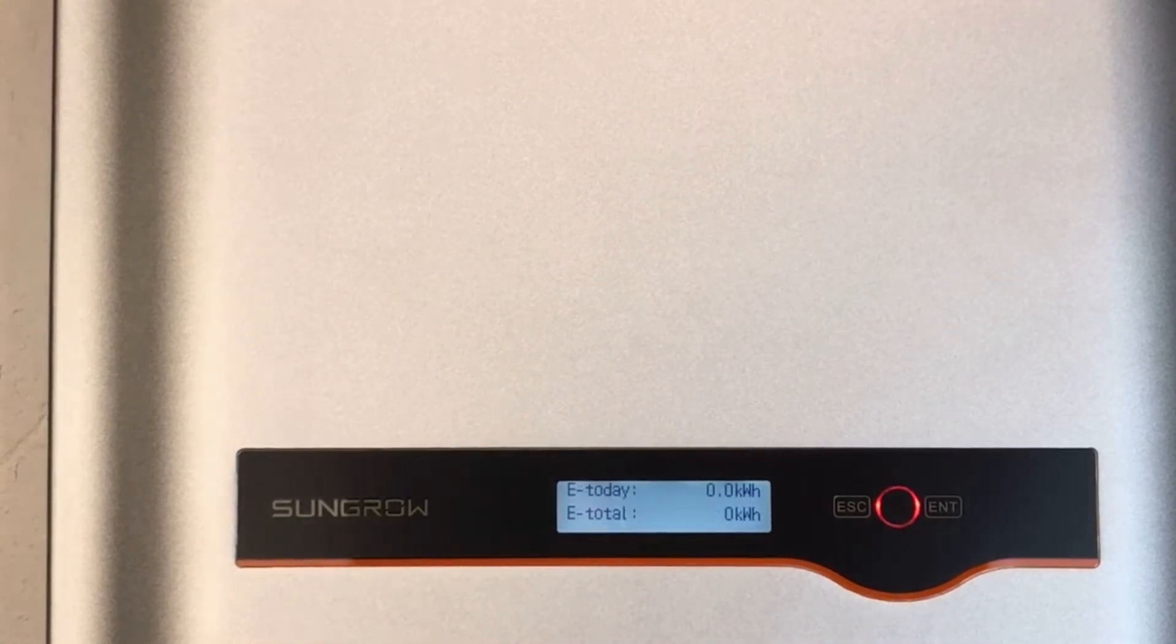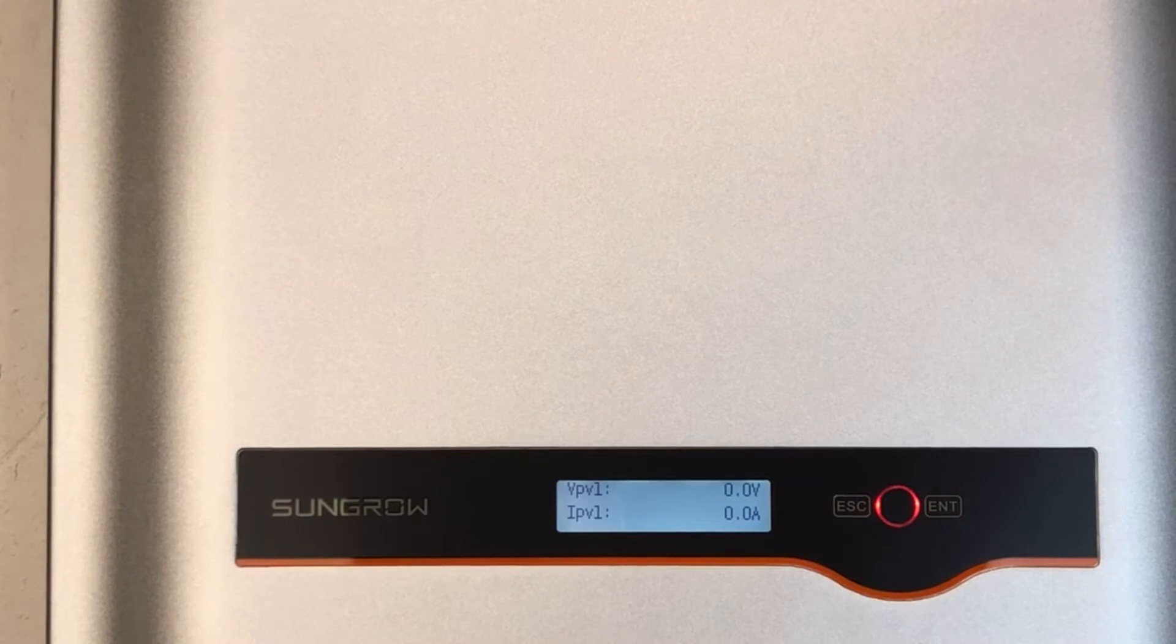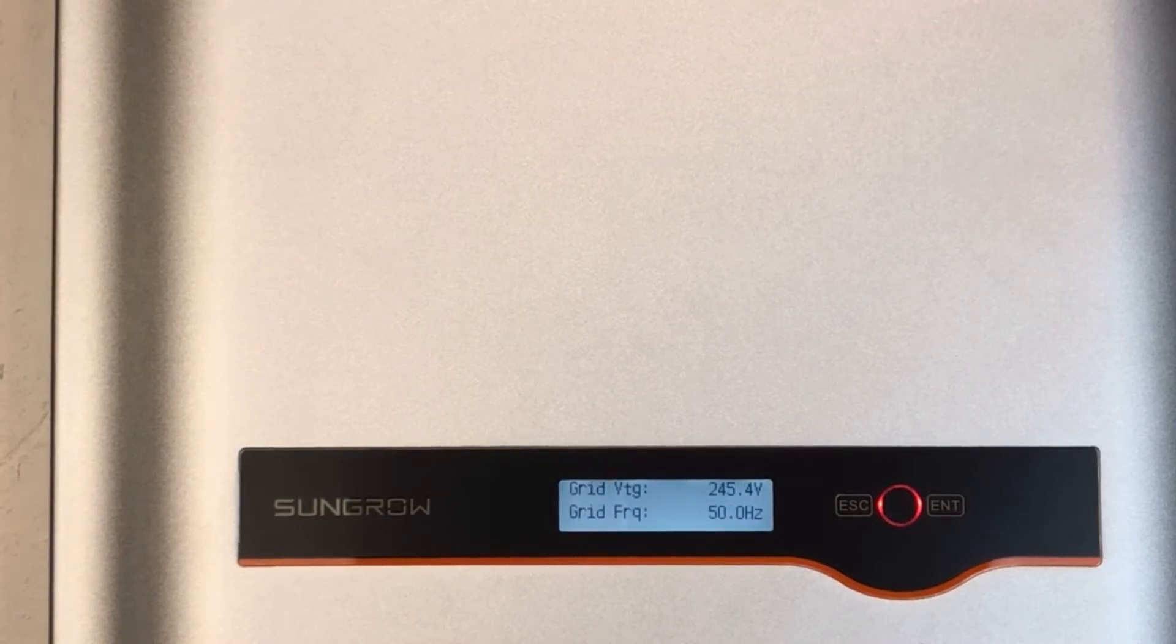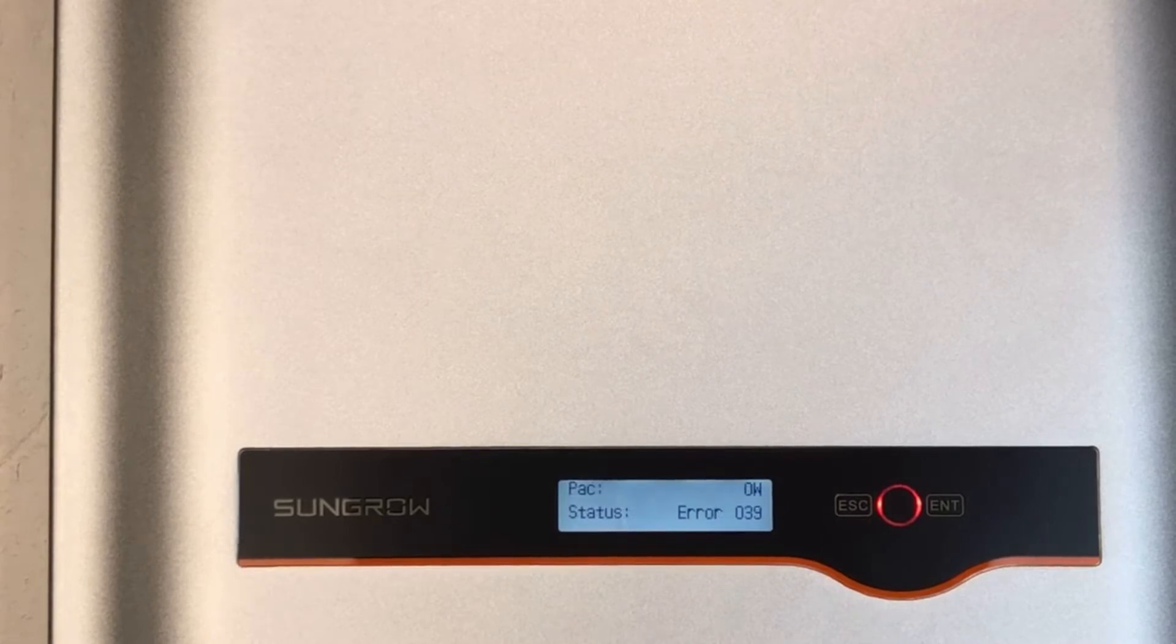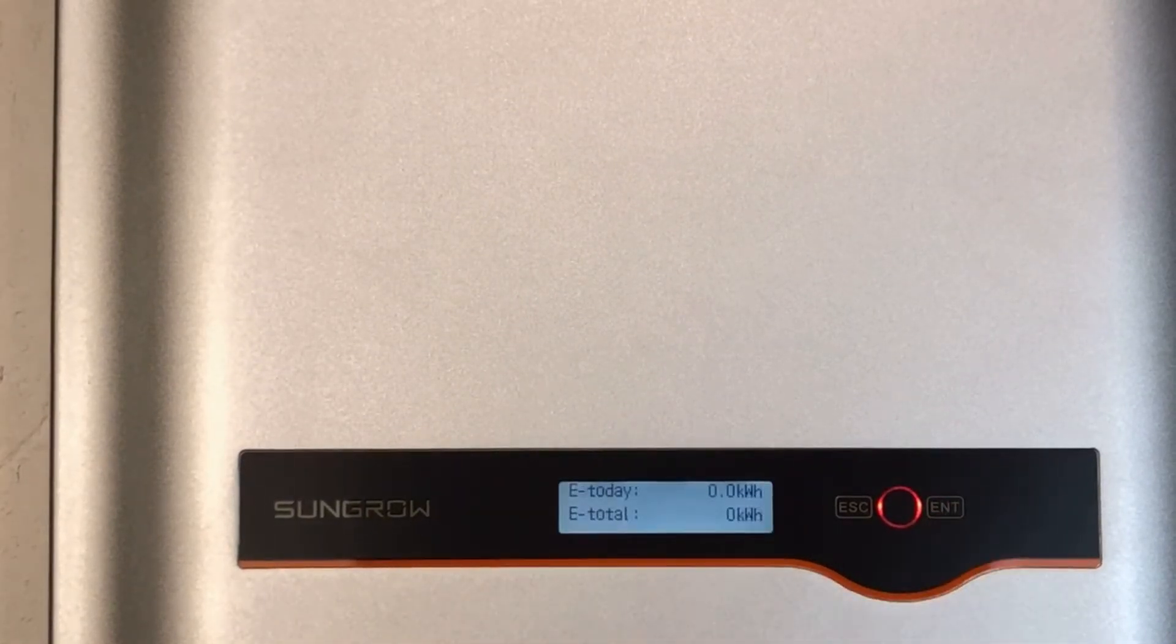Now, an error 039 message on a SunGrow inverter like this means the inverter has detected an earth fault with the system. This is an issue where DC power is being leaked to earth, and this is usually on the solar panel side of the system.